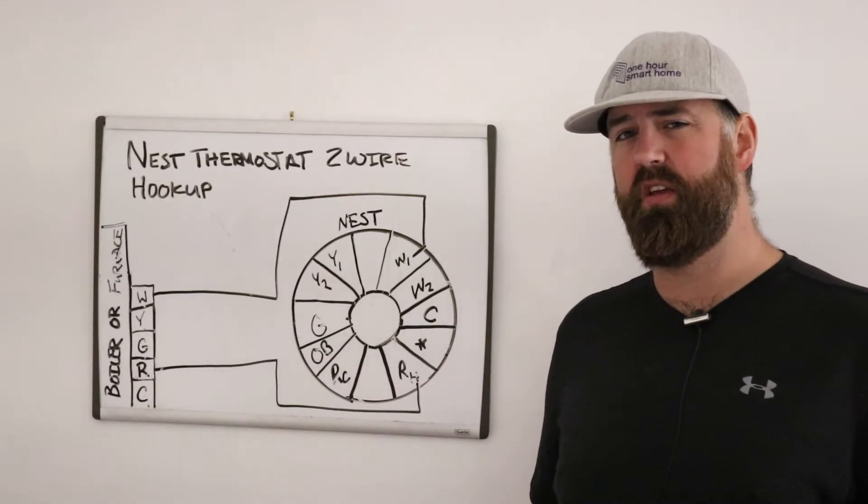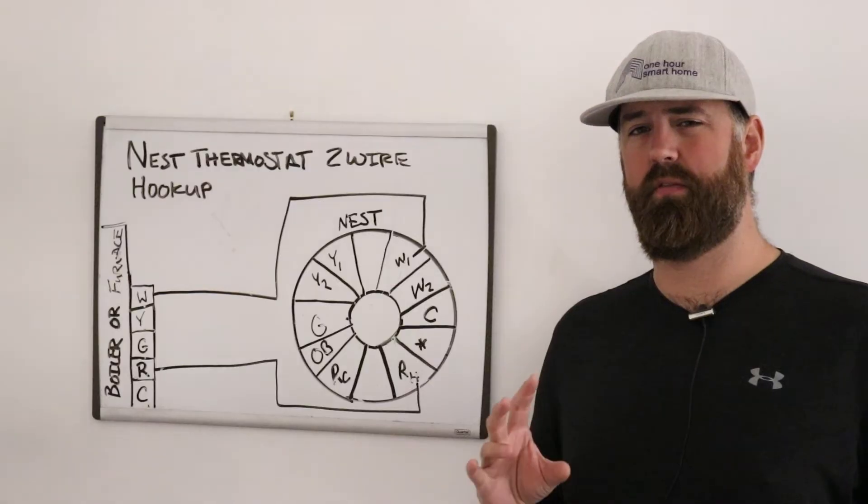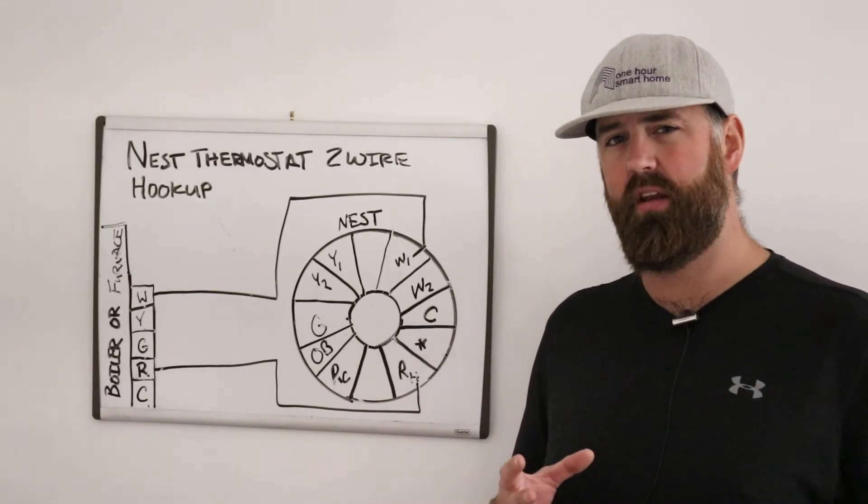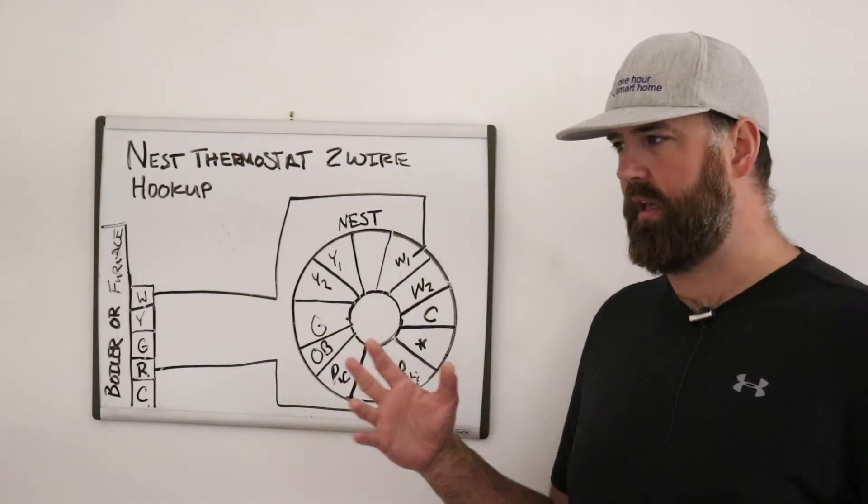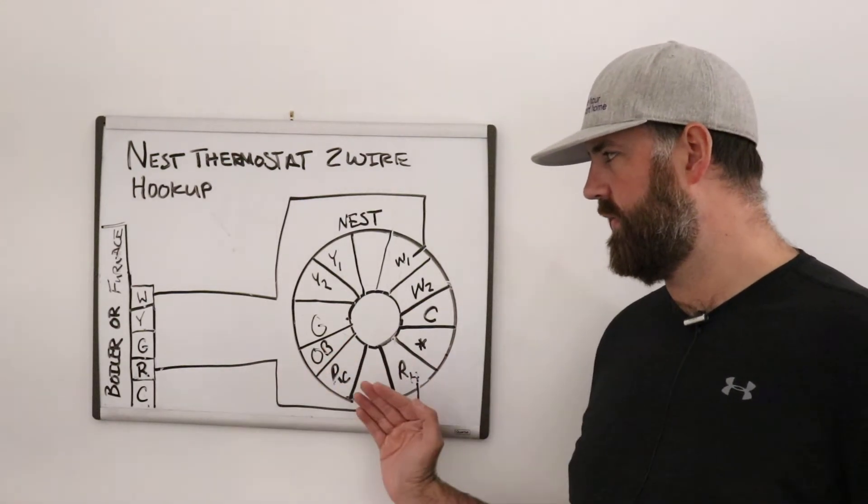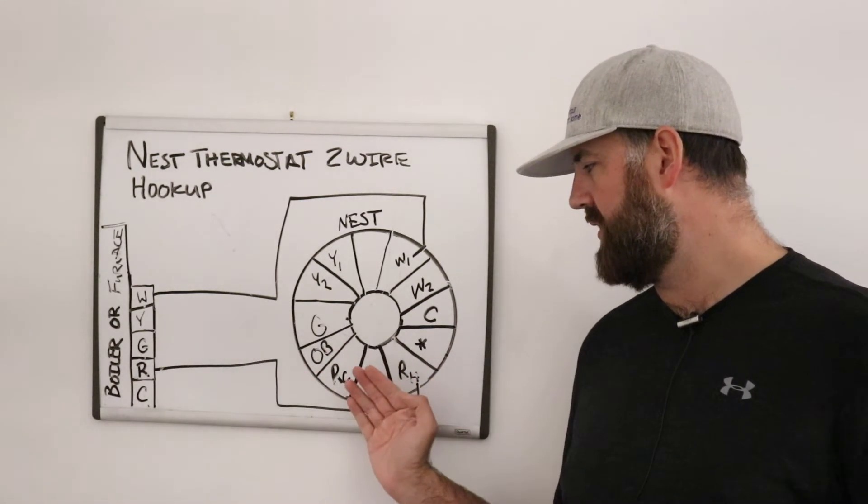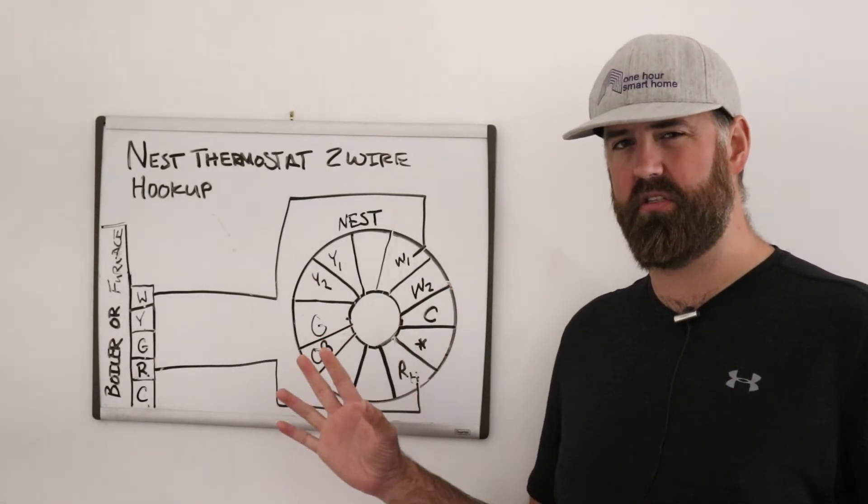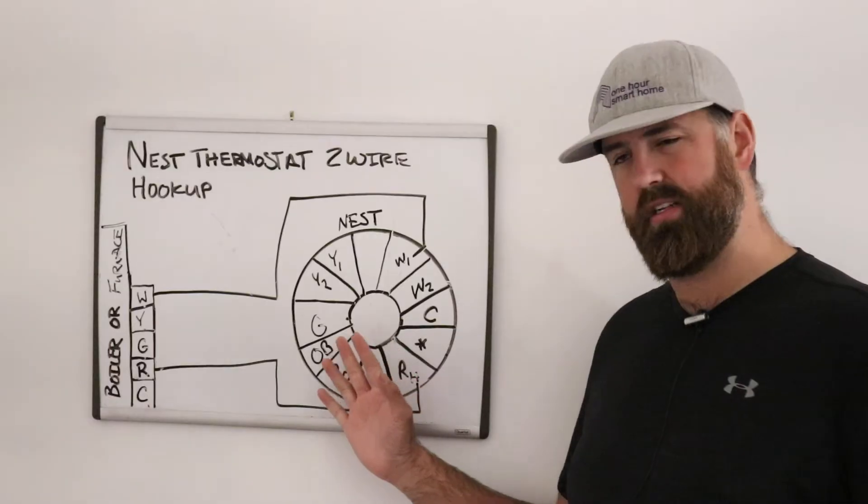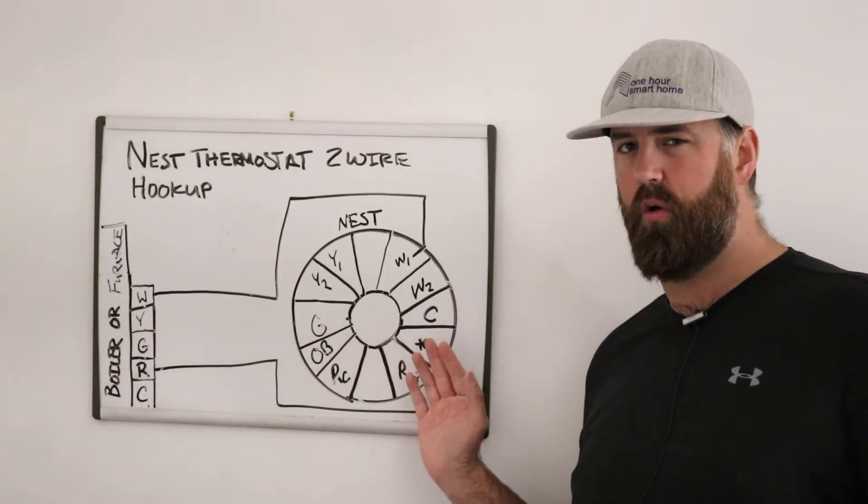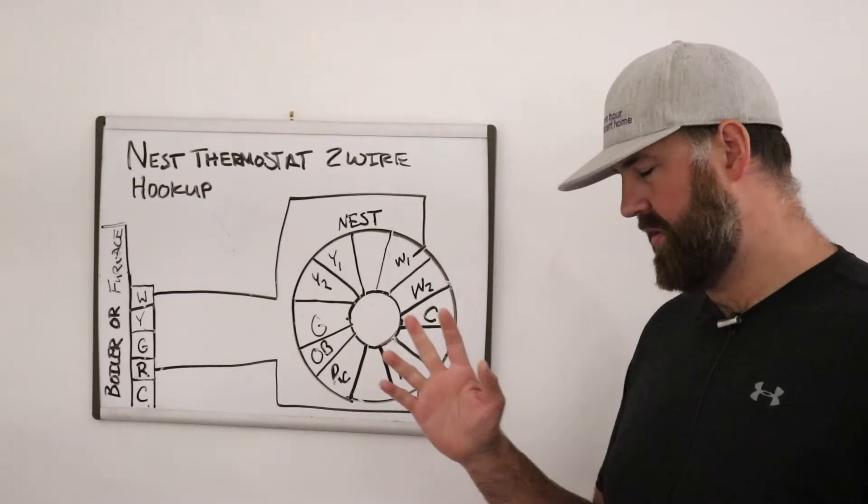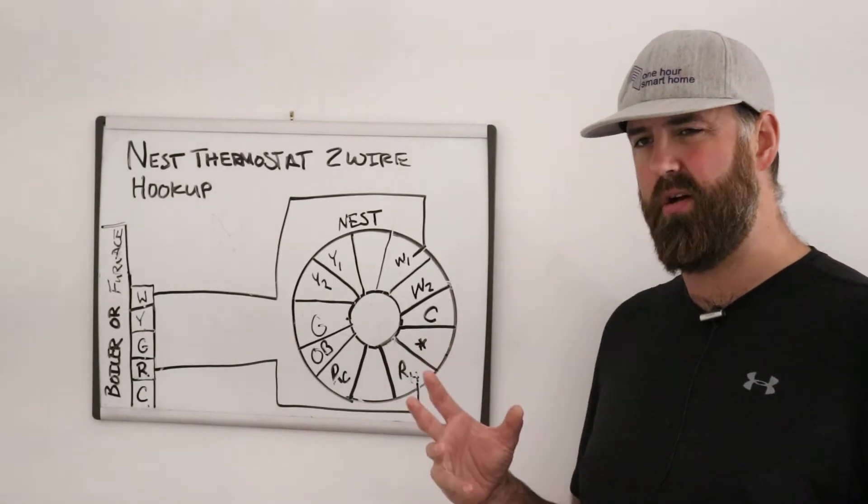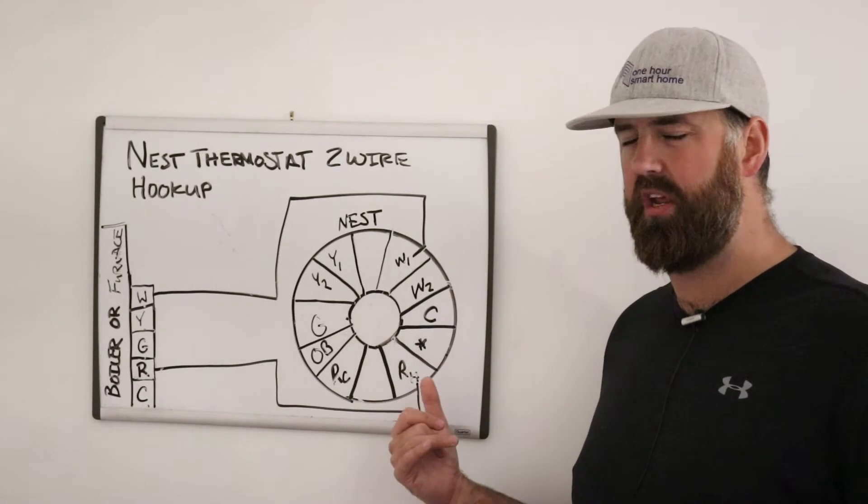O-B, that is for heat pumps. And that controls the reversing valve on the heat pump. RC, like we said, that is power. It can be used to power from your boiler or from your furnace. But the convention is meant for power from a cooling system. But with the case of the nest, you can put the power in RC or RH, it doesn't matter when you have just a two wire system. RH, that's power again. That's just power input. RH stands for heating power.